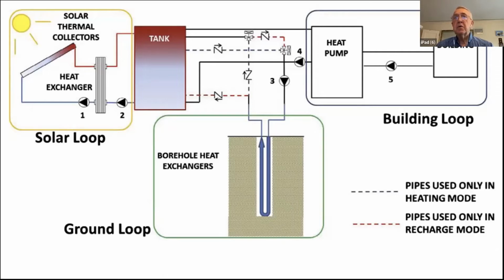Again, drilling into the ground and putting in plastic pipe where water goes down on one side and comes back up on the other side. So the heat pump in this building has a choice of water that comes from the solar thermal collection or water from the borehole heat exchangers. This design has another very good feature, which is that in the summer, when it's really hot and the sunshine is very, very strong, the building doesn't need any more heat. It's got plenty of heat. So what do you do? Here's what you do. You turn that pump number 3 on and you pump really nice warm water into the borehole heat exchanger loop.